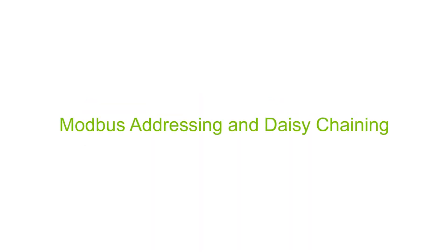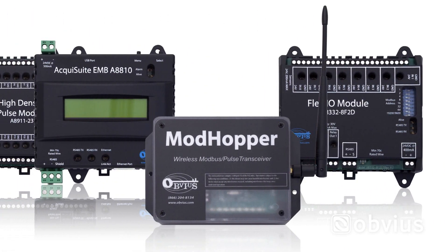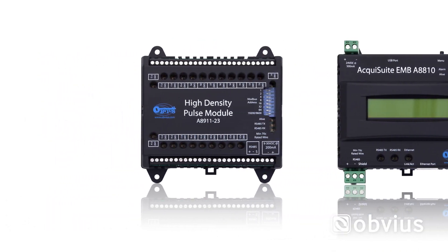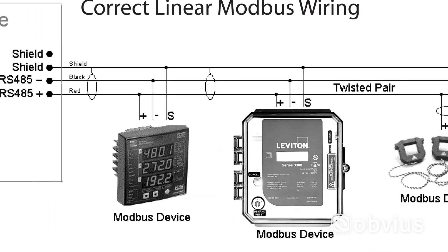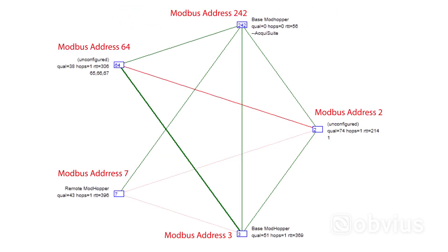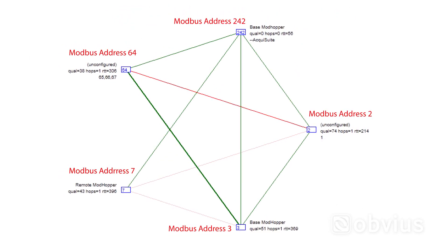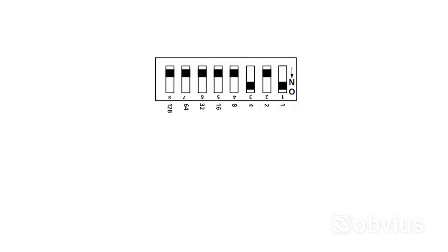This video will cover how to set Modbus Addressing and Daisy Chaining of Modbus RTU devices. Modbus Addressing is used to identify different Modbus RTU devices on a particular network. It is important that all Modbus devices on the same network have a unique Modbus Address.